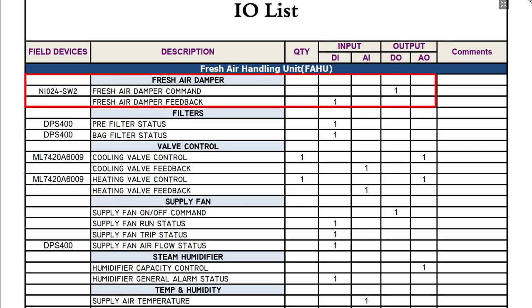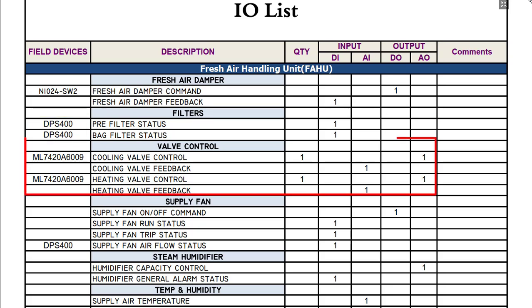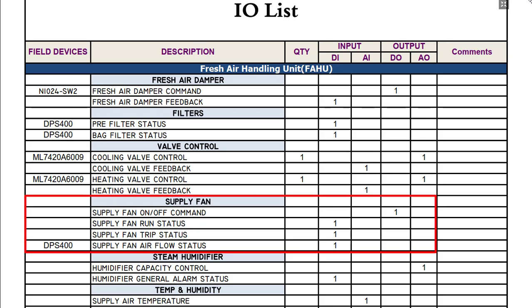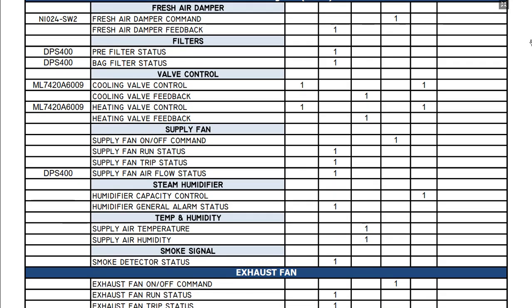First, we have the fresh air damper with command and feedback — these are DO and DI points. Then we have filters: pre-filter and bag filter, using DPS 400 differential pressure switches, both are DI points. Then we have valve control for the cooling valve and heating valve, with feedback monitoring — these are analog output and input points, with the valve actuator model numbers mentioned. Then we have supply fan points: supply fan on/off command, run status, trip status, and airflow status. Similarly, other points are shown. I think you have got the idea of how this IO list is built and what information it contains.